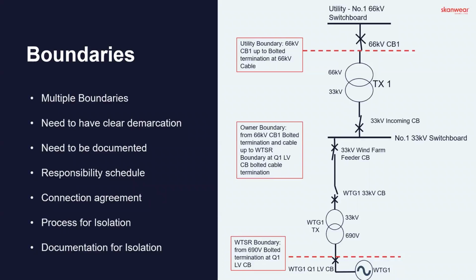Likewise, we've got an example downstream where the MV or HV transformer falls under the owner's electrical safety program and safe system of work, but it goes into the wind turbine safety rules boundary at the main Q1 circuit breaker, in this example the WTG1 Q1 LV circuit breaker. So if I wanted to work on the WTG1 transformer and conduct my high voltage or medium voltage maintenance, I would need a cross-boundary isolation to be done by the wind turbine safety rules provider to make sure that it is suitably isolated for my works.